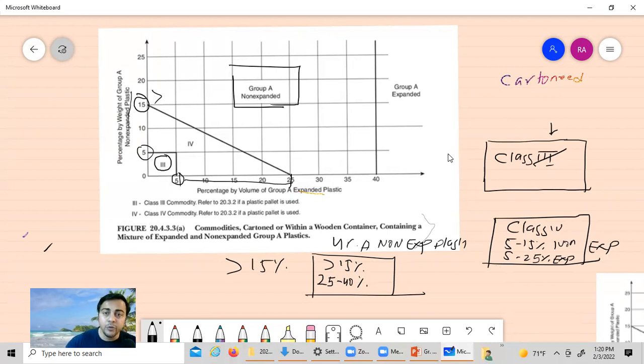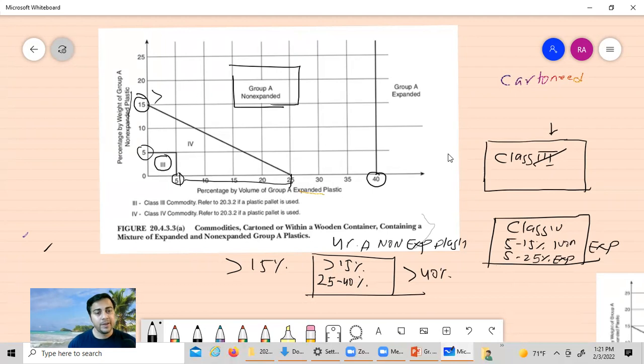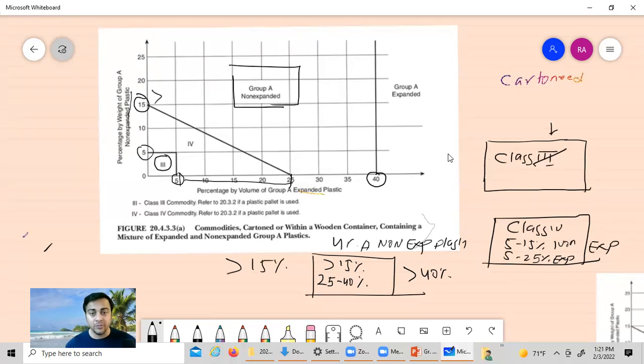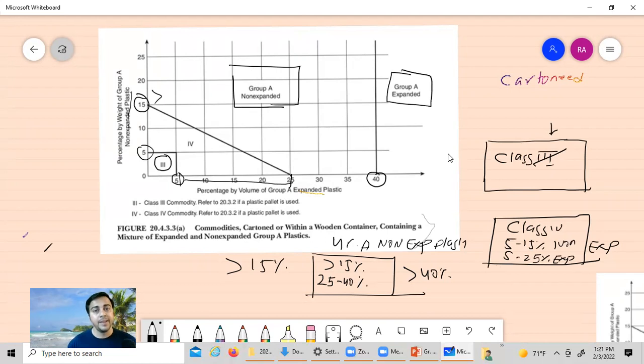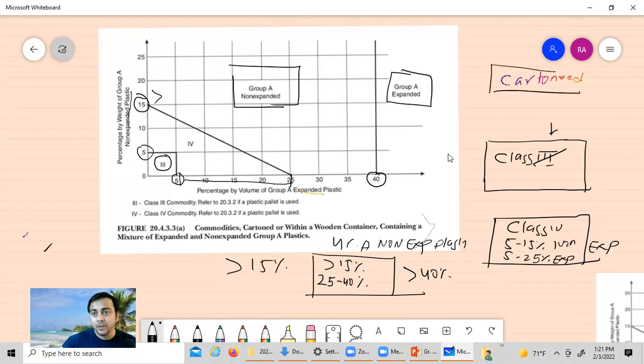Anything higher than 40% by volume — for example, products with expanded packaging items where the density is reduced — should be considered as Group A expanded plastic. So that covers Figure 2433A. Remember, this figure is just for cartoned commodities. Next, we'll be moving on to exposed commodities.